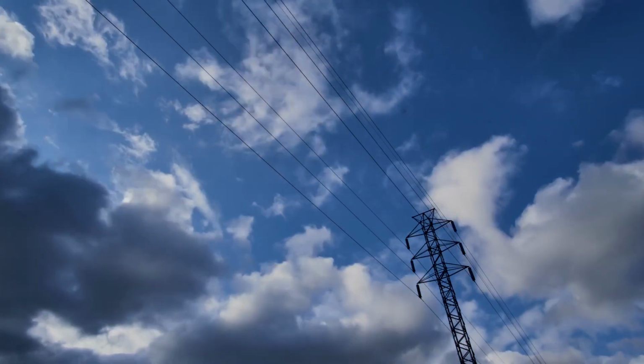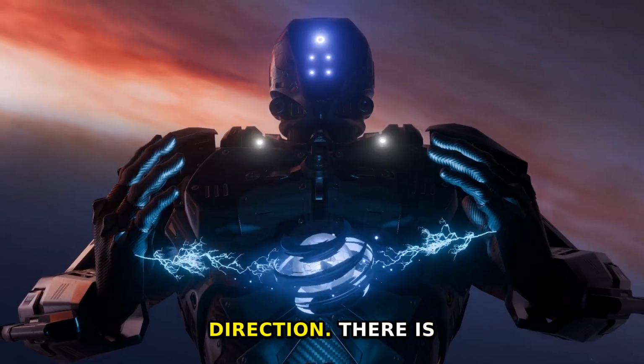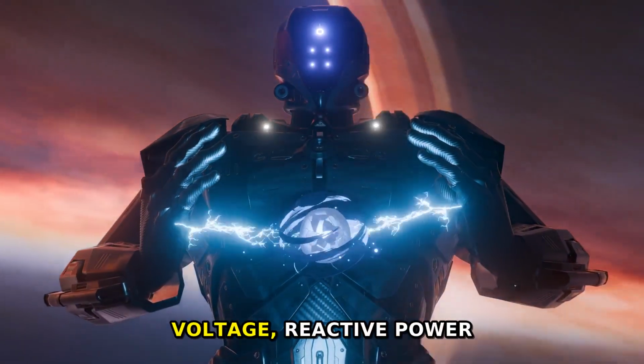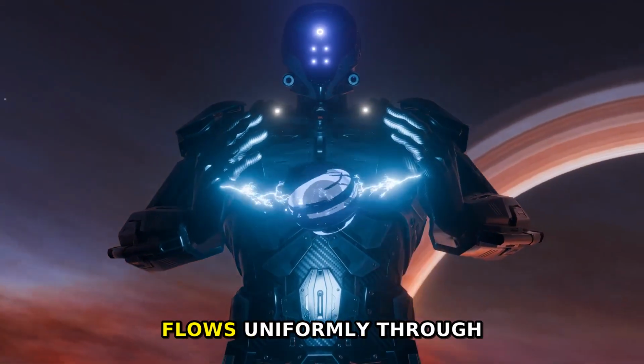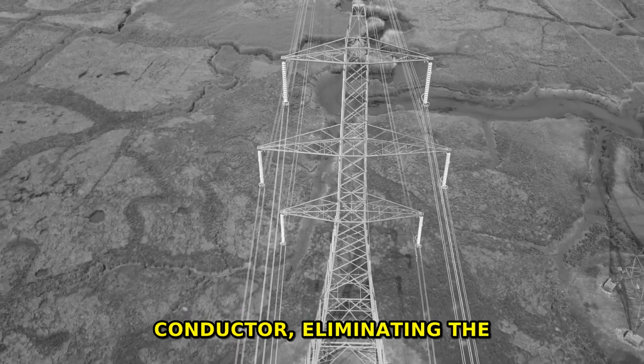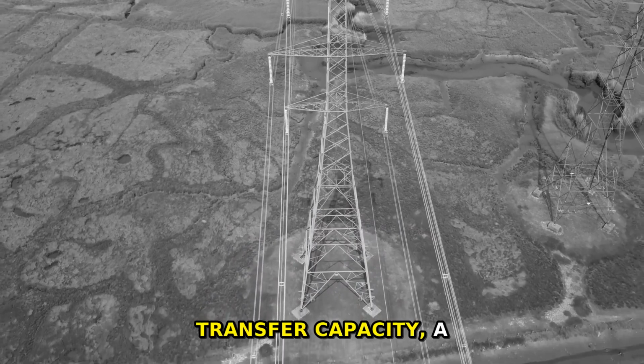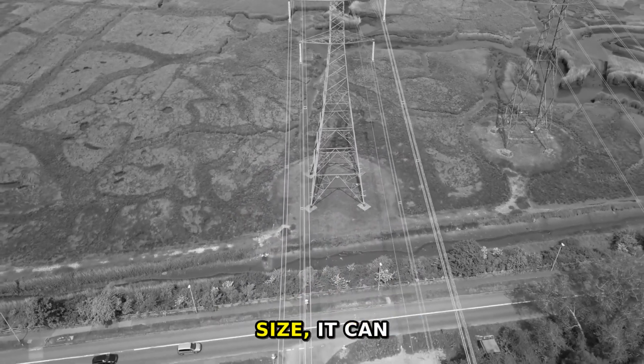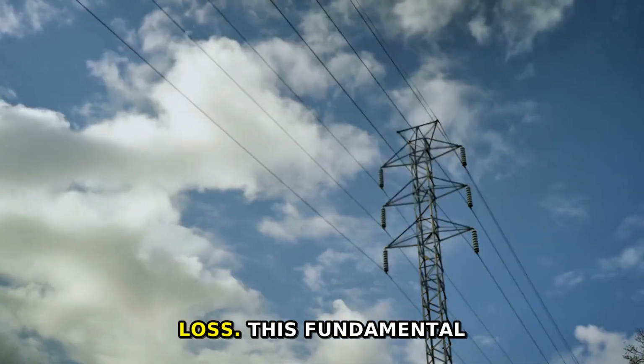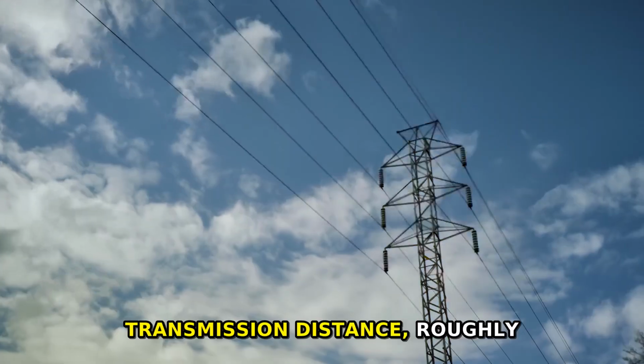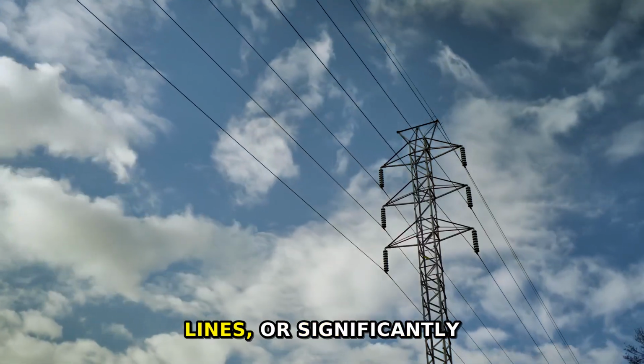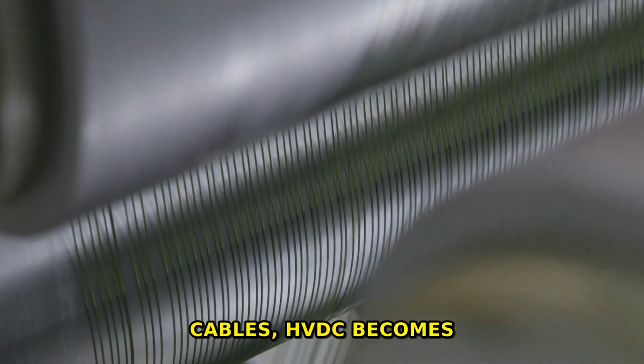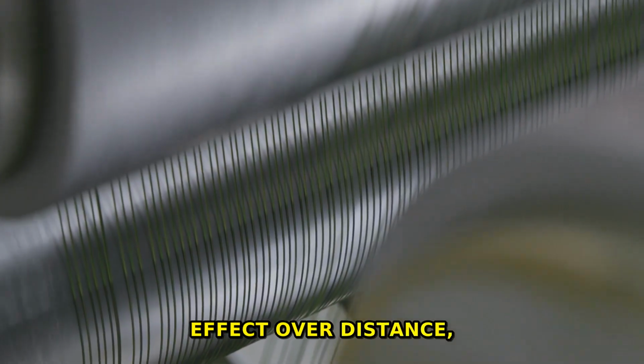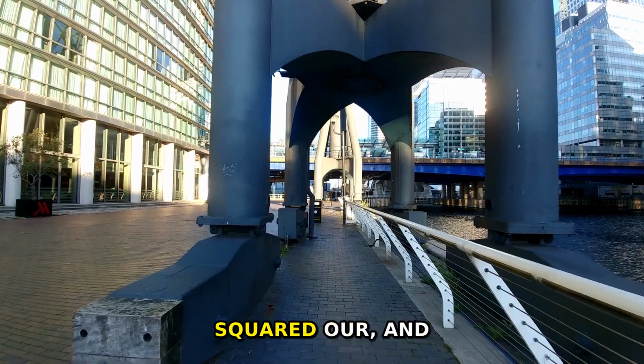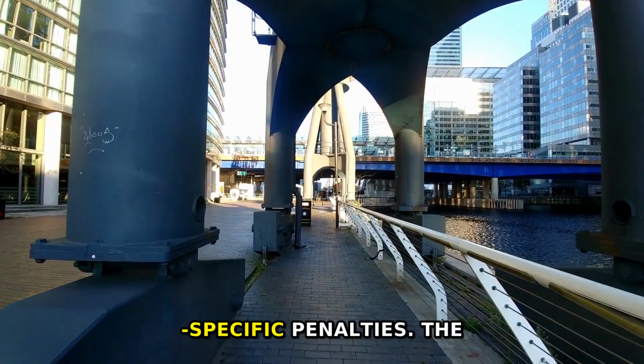Now consider direct current. With direct current, the electrons flow in one continuous direction. There is no phase difference between current and voltage, so reactive power simply does not exist. The current flows uniformly through the entire cross-section of the conductor, eliminating the skin effect. For a given power transfer capacity, a DC line can use a smaller conductor, or for a given conductor size, it can carry more useful power with less loss. This fundamental difference is why, beyond a certain transmission distance, roughly 700 to 800 kilometers for overhead lines, or significantly less for submarine cables, HVDC becomes more efficient than AC. While AC suffers continuous, cumulative losses from reactive power and skin effect over distance, HVDC losses are primarily resistive, I²R, and are proportional to length but without these additional AC-specific penalties.